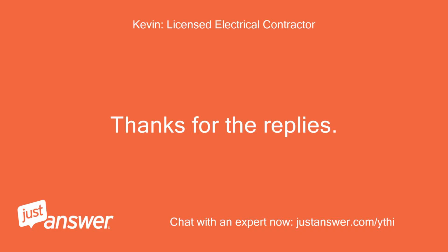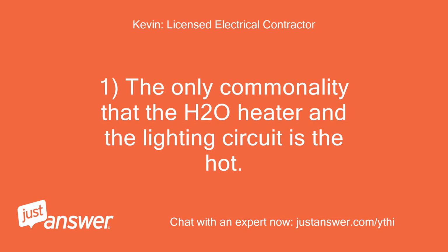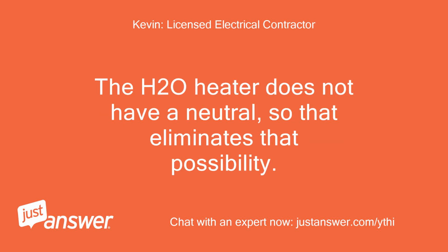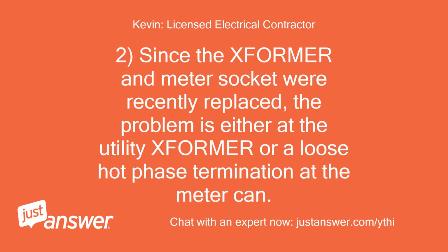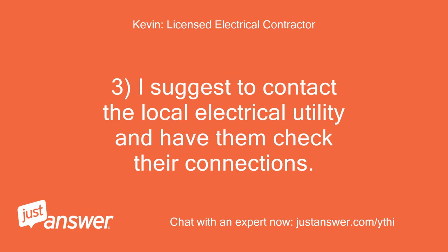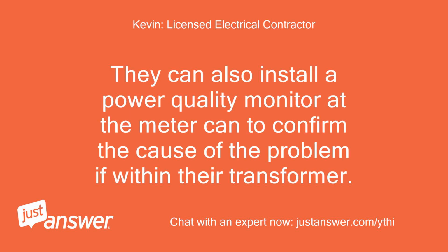Thanks for the replies. 1. The only commonality that the H2O heater and the lighting circuit have is the hot. The H2O heater does not have a neutral, so that eliminates that possibility. 2. Since this transformer and meter socket were recently replaced, the problem is either at the utility's transformer or a loose hot phase termination at the meter can. 3. I suggest to contact the local electrical utility and have them check their connections. They can also install a power quality monitor at the meter can to confirm the cause of the problem if within their transformer.